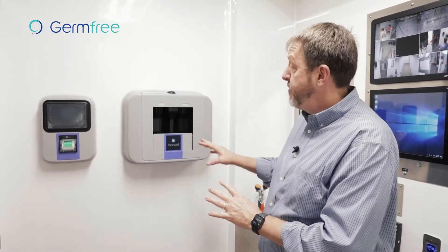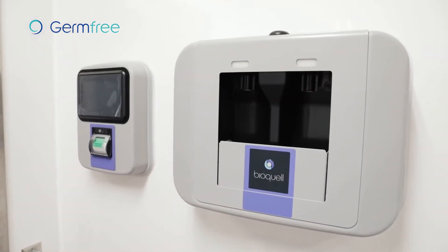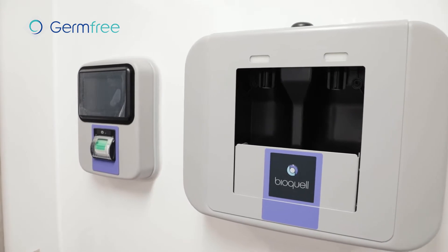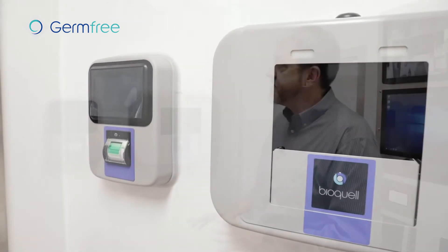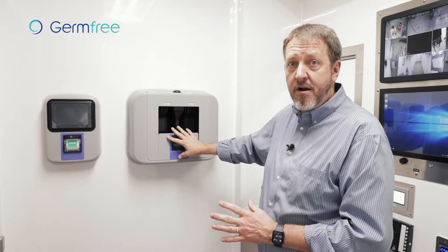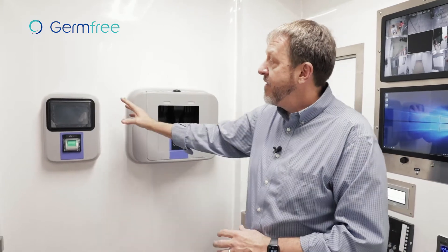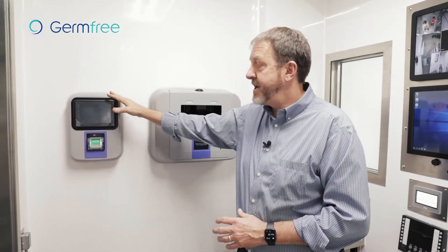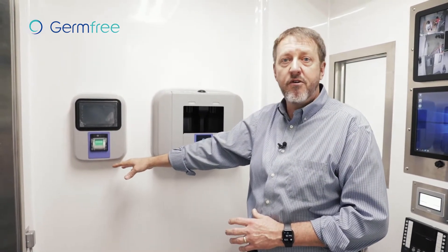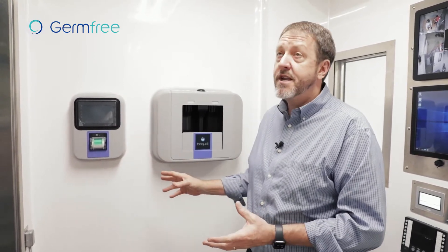One of the more unique features is we partner with Bioquell to put in a completely integrated VHP decontamination system into this trailer. It's an option for this trailer in any of its configurations. As it's set up now, you put your sterilant in this device right here that's piped into the actual delivery system in the back. The control system and data collection happens up here, so it's completely GMP compliant — a very unique system.